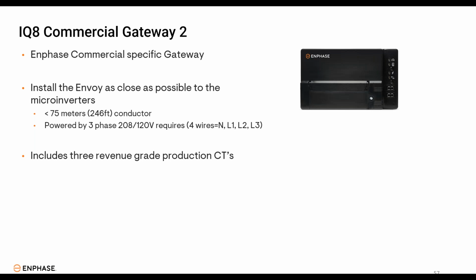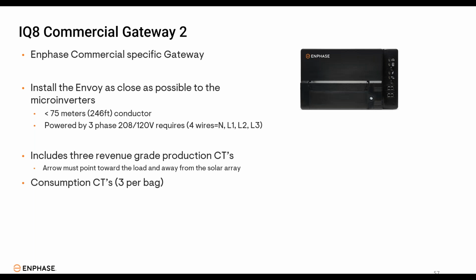It includes 3 revenue grade production CTs that are rated for 400 amps. When they are being installed, the arrow must point toward the load and away from the solar array. If you want to monitor and measure the entire site's loads, we do have optional consumption CTs that are rated for 600 amps. And if you have sites that are larger than 600 amps or other issues that require a different monitoring, we have different meters that we use to send information from the point of connection to our gateway.